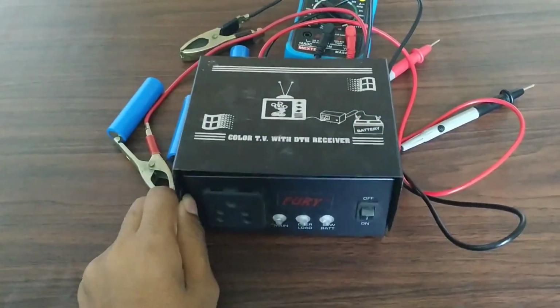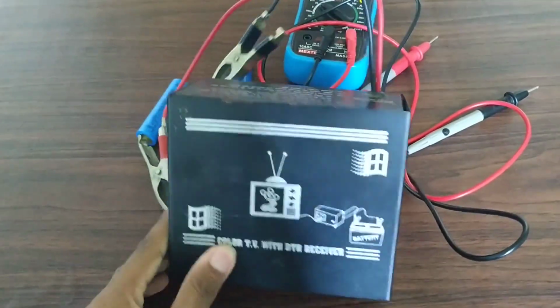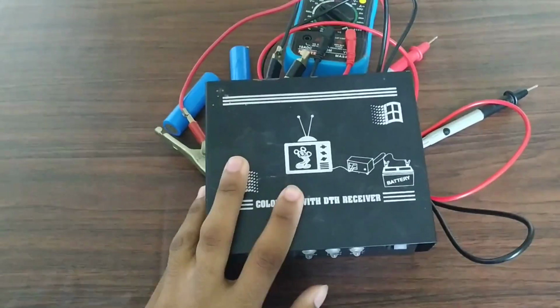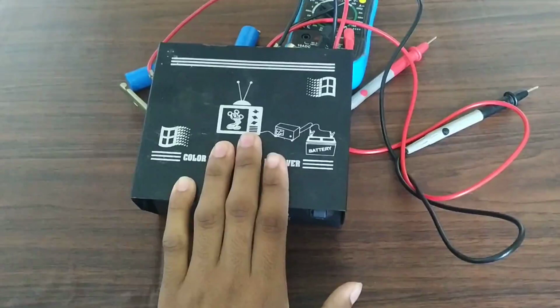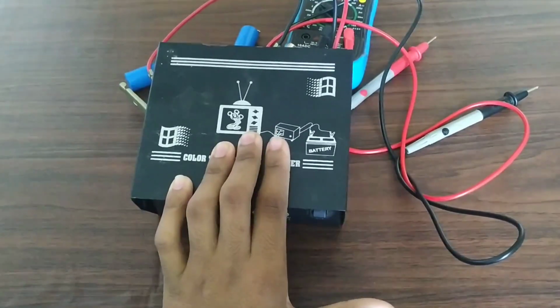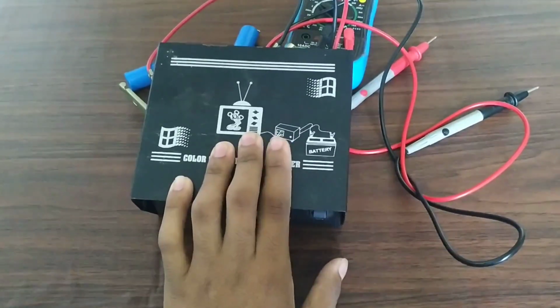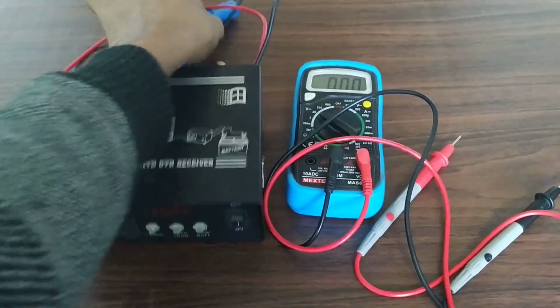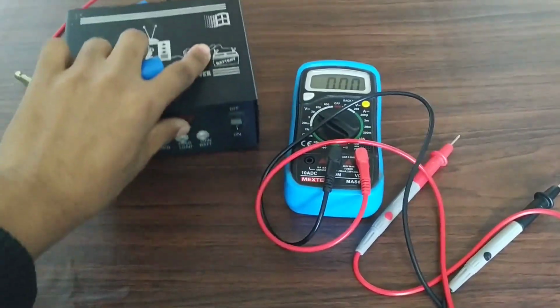There's no voltage or current rating listed on this box, so I'll test it to see if it's good or not. The link to this product is in the description if you want to check it out. First, we have to measure the terminal voltage and capacity of each battery.